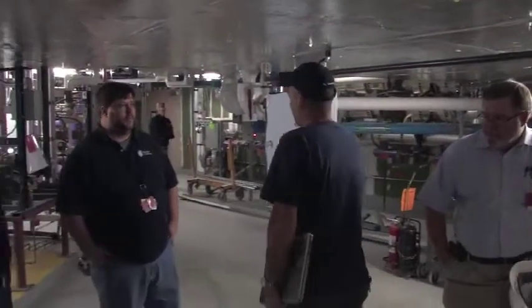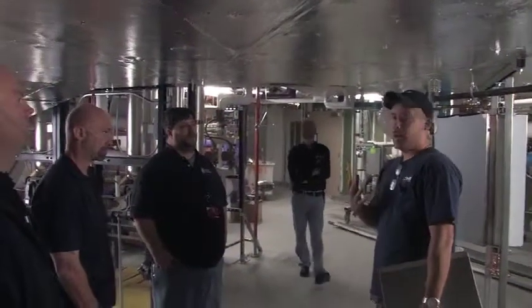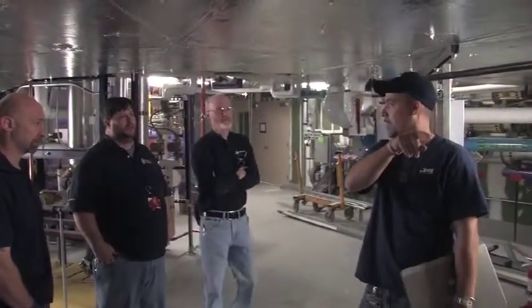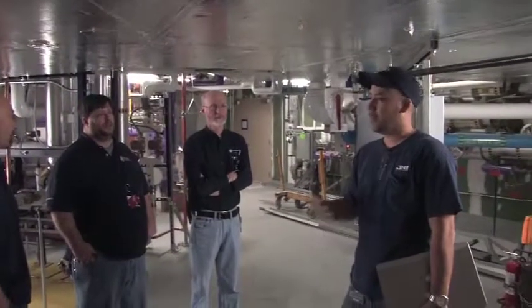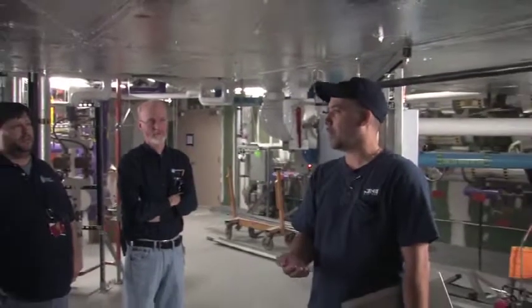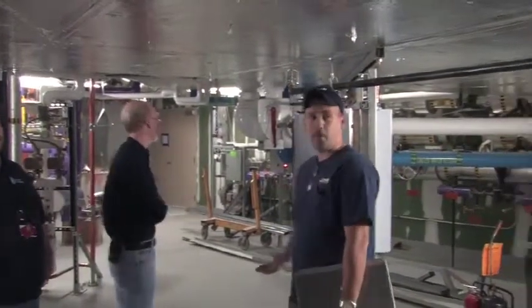So pretty much you have a fan that's going to be off. If the temperature rises above the set point that is adjustable at that thermostat, the fan's going to come on, try to bring the temperature down to the thermostat set point, and then when it goes below its differential, it's going to shut off. And that's pretty much the operation of it.